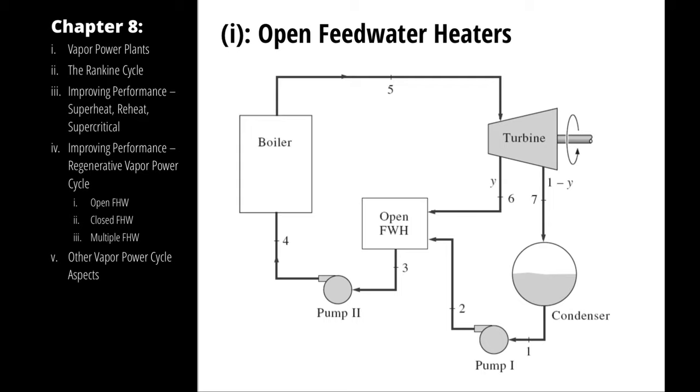What we do here is extract some steam early out of the turbine, run it through a regenerator, either of the open feed water heater or closed feed water heater variety depending on whether it mixes or not, and reunite it with the stream it was extracted from before it goes into the boiler again.